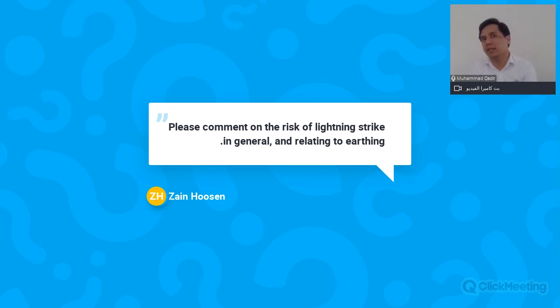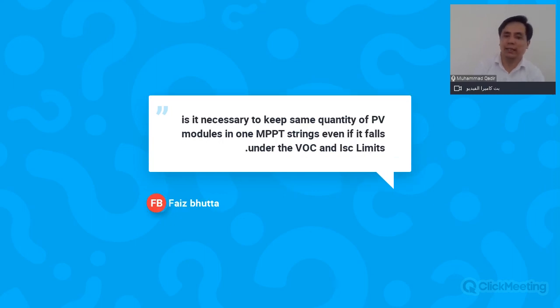But if lightning directly strikes your solar inverter, that is not a case of SPD protection. That is the case where lightning is directly touching your solar inverter. That will definitely damage your solar inverter. So you are advised to use lightning arresters, which you can read about, and you can install them so that if you have a lightning prone PV plant location, you are mitigating the risk of lightning directly touching your solar inverter.